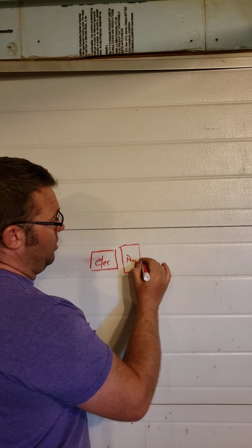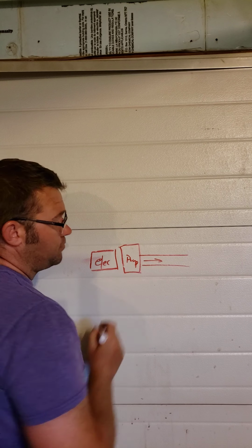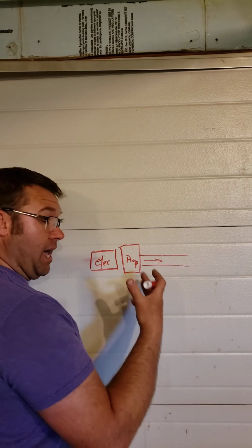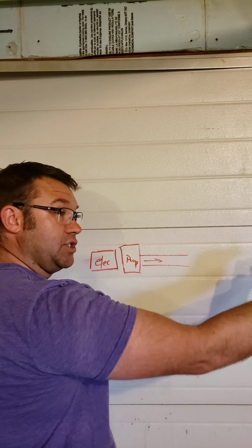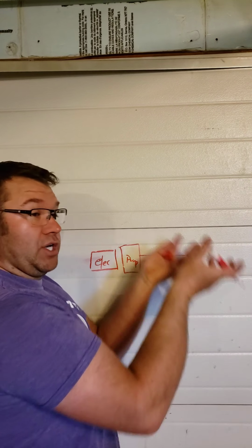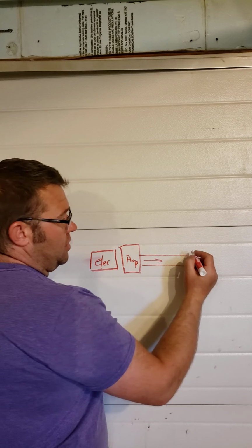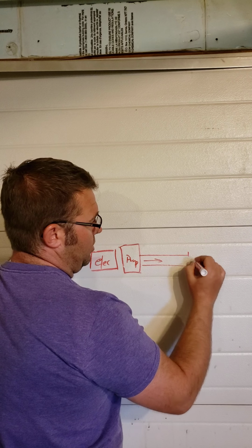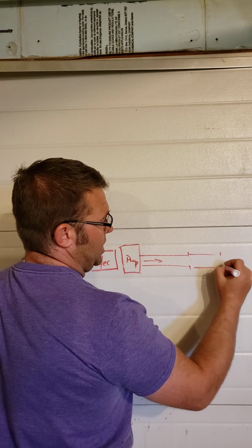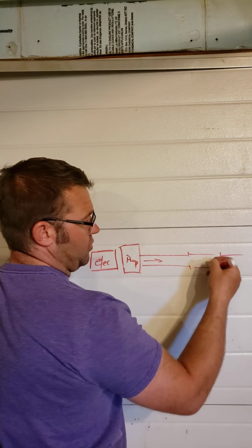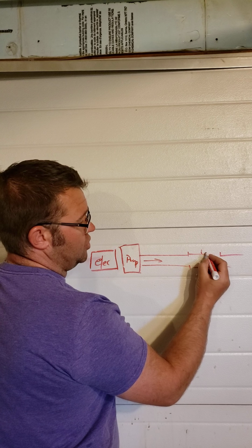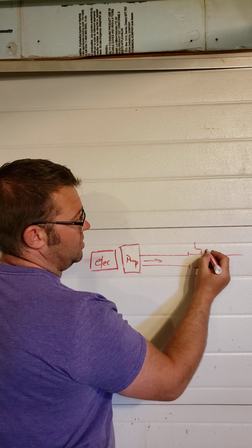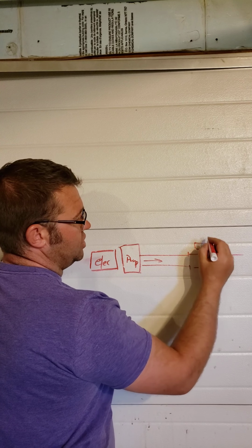Now, that pump creates flow, and pressure if there's restriction. The restriction actually creates pressure. So the jets' restrictions create the pressure buildup for us. On this pump, there is a pressure switch in a little heater circuit. It just happens to be threaded into the same spot where the heater is. Now, that pressure switch is a switch.